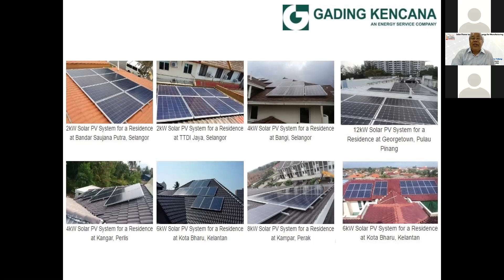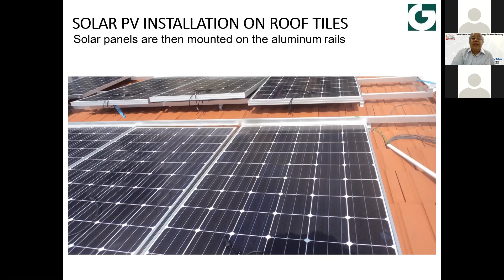This picture shows us doing the installation. We make sure all the cables are tested before connection, because we want to confirm every module we install is good and will work properly. Before connecting, we test the system and check the IV curve first, before it's connected on the roof.